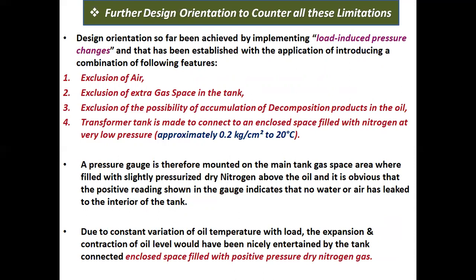That is, one, exclusion of air. Two, exclusion of extra gas space in the tank. Number three, exclusion of the possibility of accumulation of decomposition products in the oil. Number four, the transformer tank is made to connect to an enclosed space filled with nitrogen at very low pressure, approximately 0.2 kg per centimeter square at 20 degrees centigrade.